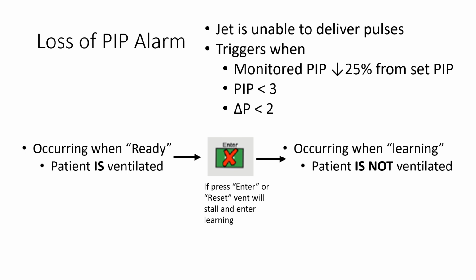If the loss of PIP alarm occurs in the non-ready mode, the patient is not ventilated and the alarms are not active. The flow and servo pressure will completely stop to protect the patient. The ventilator will not re-engage until the Enter button is pressed. This will place the ventilator back into the learning mode and it will attempt to stabilize pressures. It is important to assess the circuit and patient before the ventilator is placed into the learning mode because if the error is not resolved, it will repeat until it is adequately addressed.